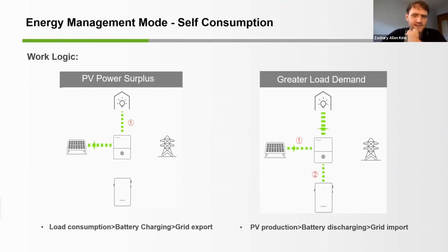So once PTO has been granted by the utility, the inverter can begin its normal operating procedures. Here we can see how the different work modes of the inverter are handling the exportation of energy. The maximize self-consumption mode ensures full support for the user's loads and charges the battery with clipped solar energy during peak PV array production. This allows the battery to discharge when the PV production is insufficient or not present to power the user's loads. And this is turned on by default. So this is the default setting of the inverter and the battery.